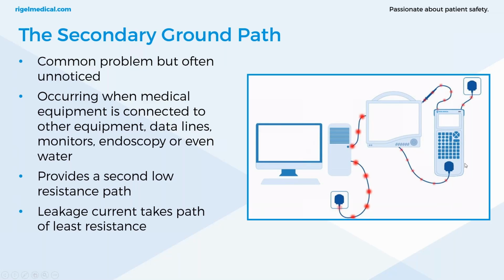And the safety analyzer is measuring a much lower value because the resistance is higher. There's a body model within all safety analyzers, typically 1 kilo ohm. So the electrical current is going to take the path of much lower resistance.